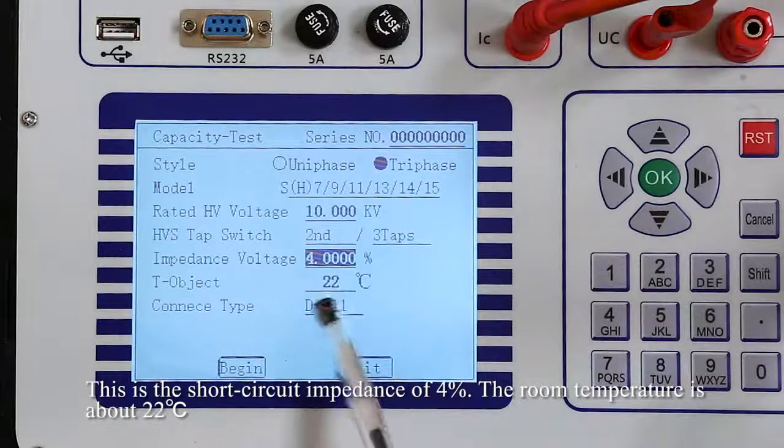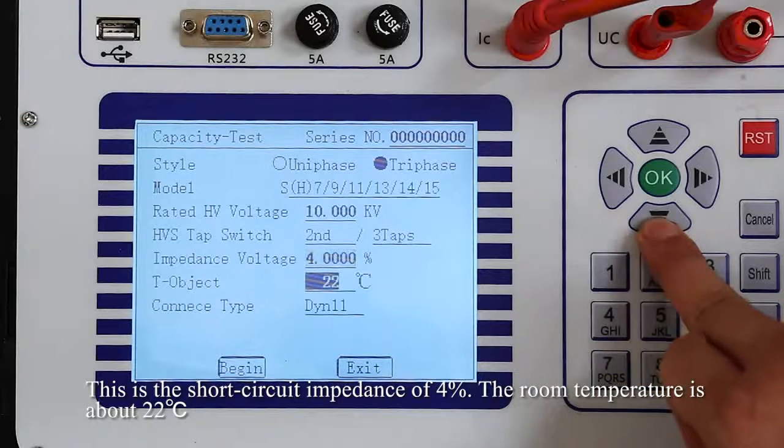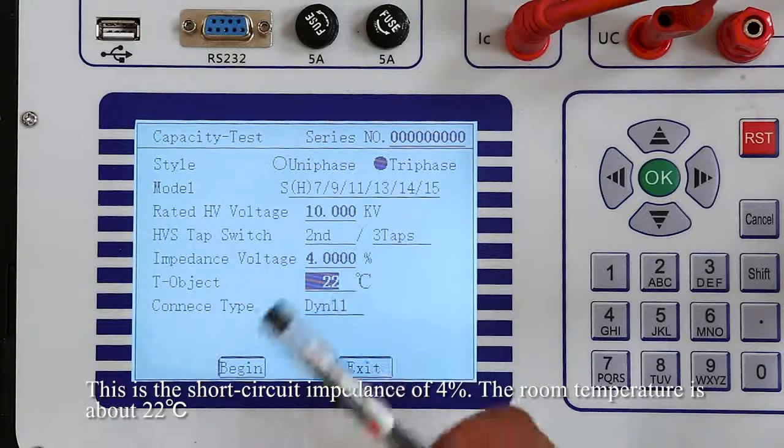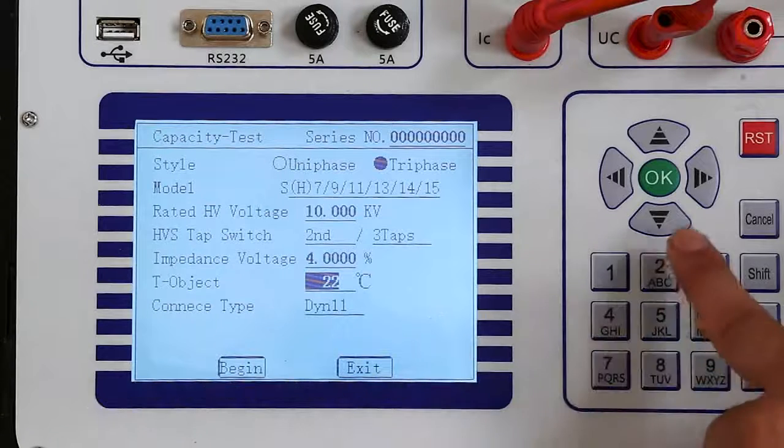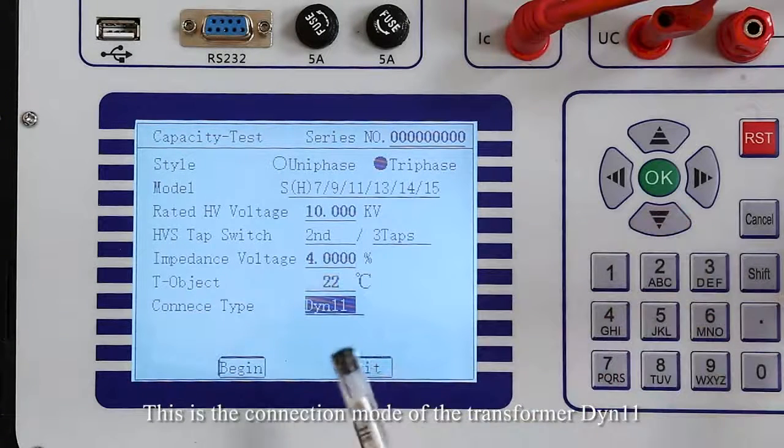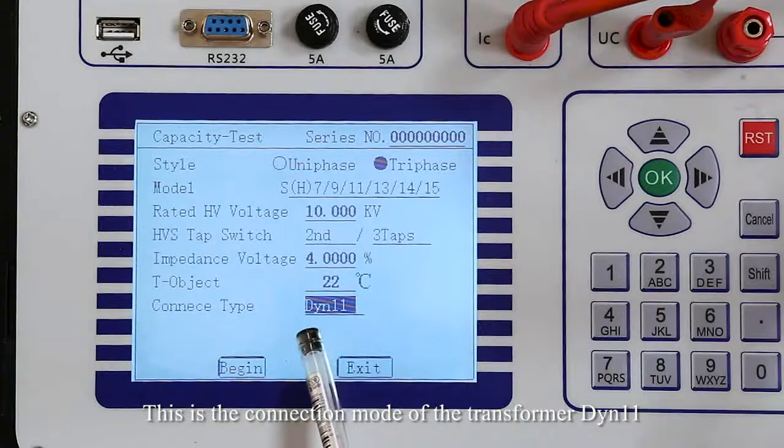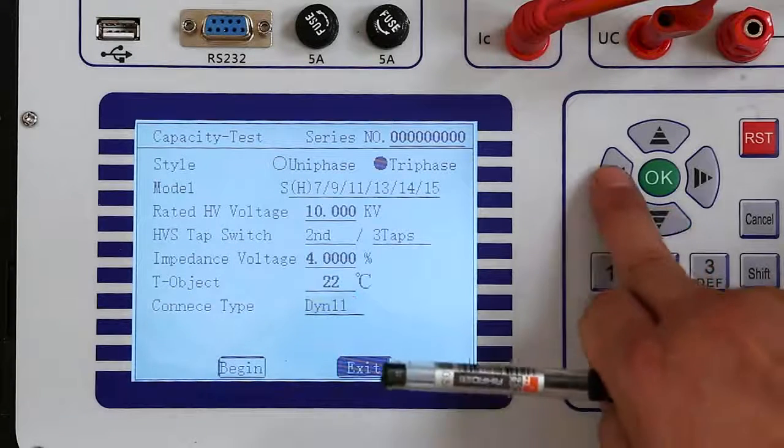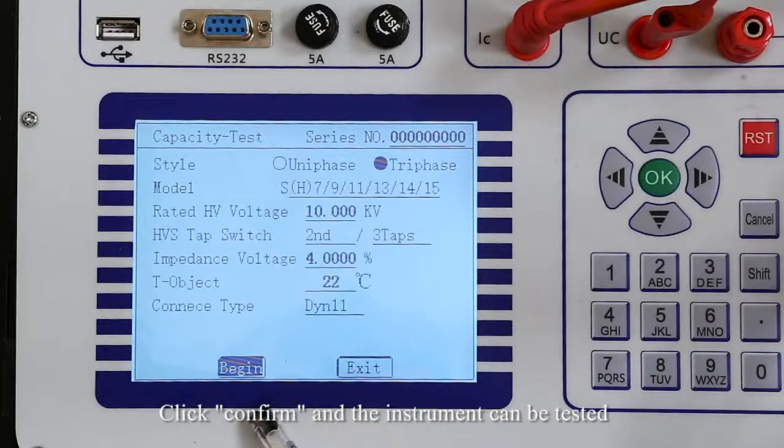This is the short-circuit impedance of 4%. The ambient temperature is about 22 degrees Celsius. This is the connection mode of transformer Dyn11. Click confirm and the instrument can start testing.